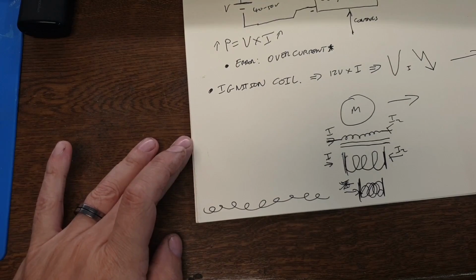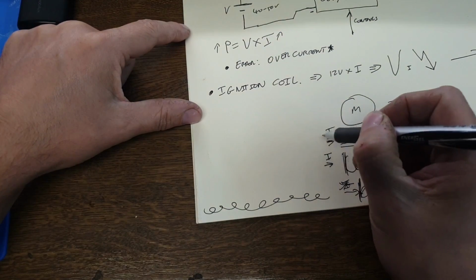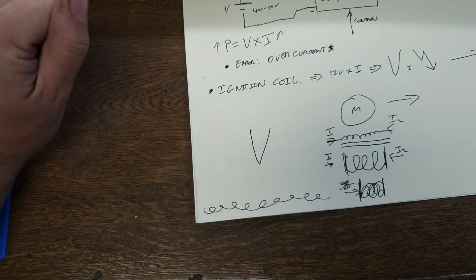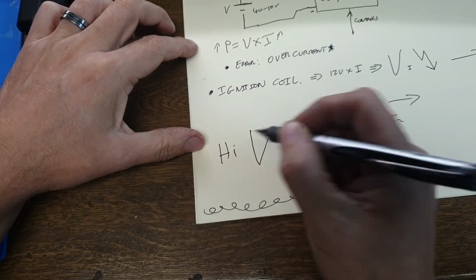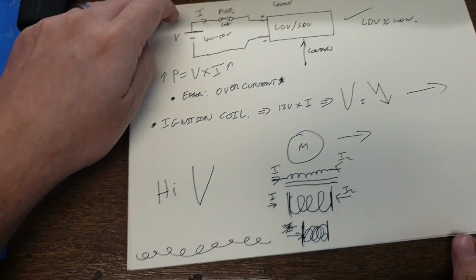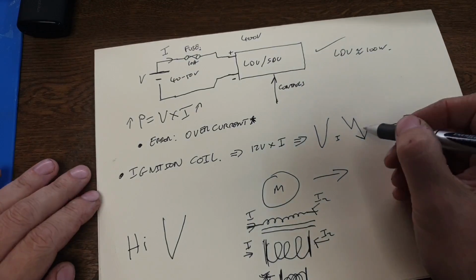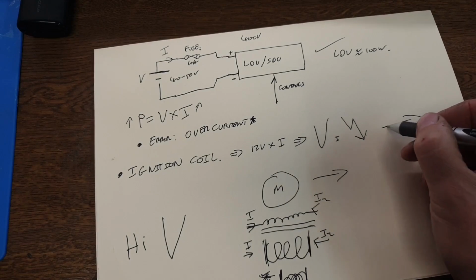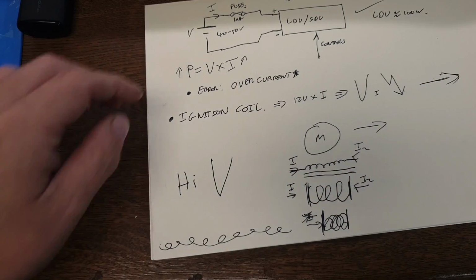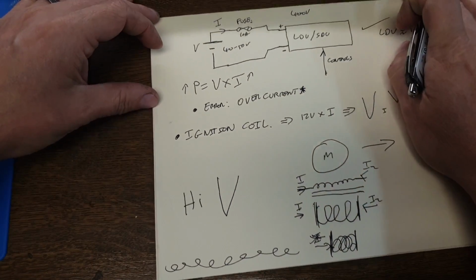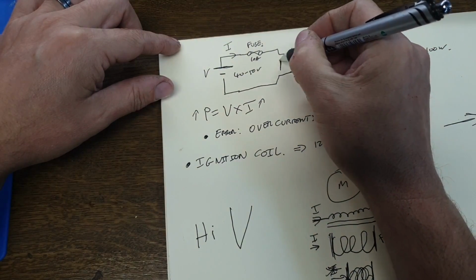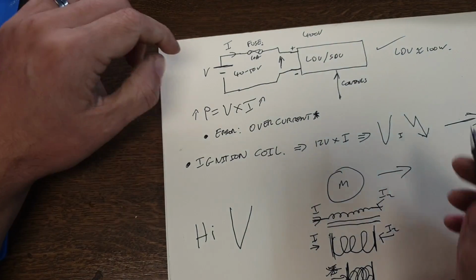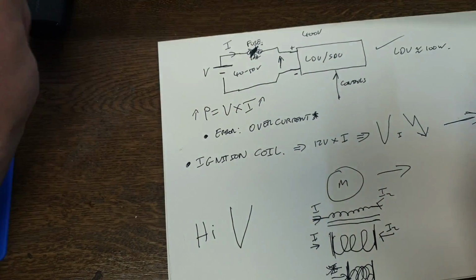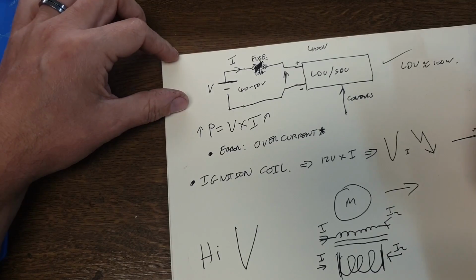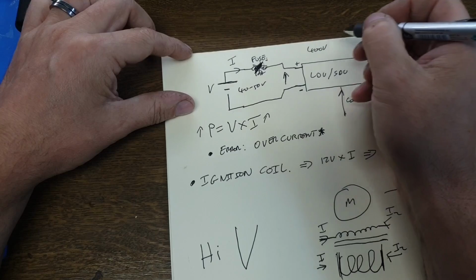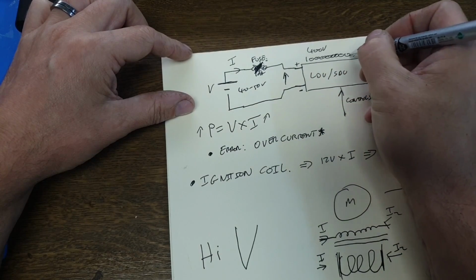Now that's the mechanical version. The electrical version is that we get a very big voltage, rock and roll—that's the same principle we have in our ignition coil that gives us spark and lets us go down the road. Sadly, if this happens in an inverter and drive unit, we get a massive voltage kick across the battery terminals. Our battery is no longer connected because the fuse has blown, so the voltage across these terminals for a very short space of time can go to ridiculous voltages.